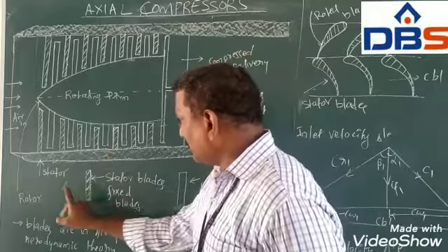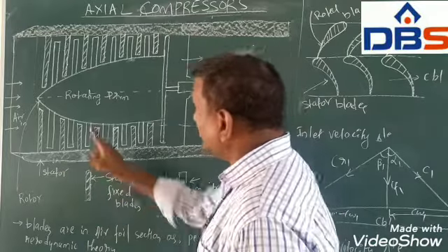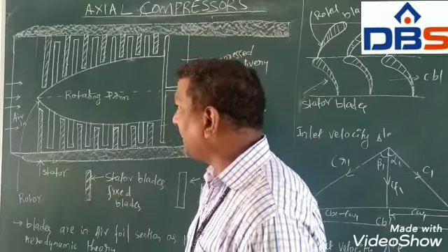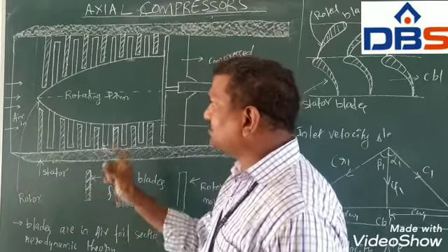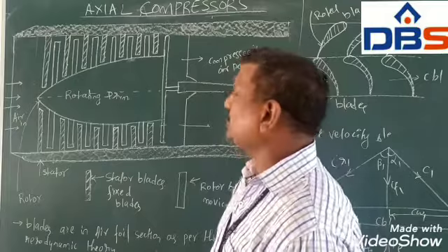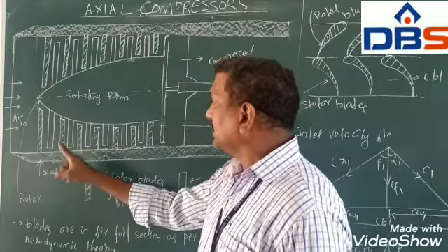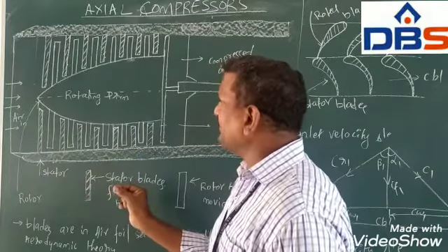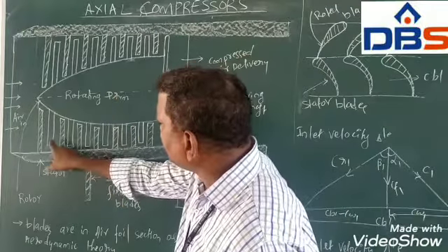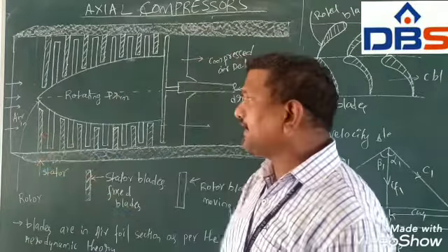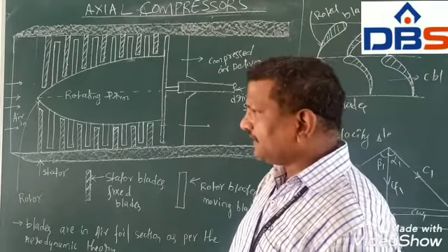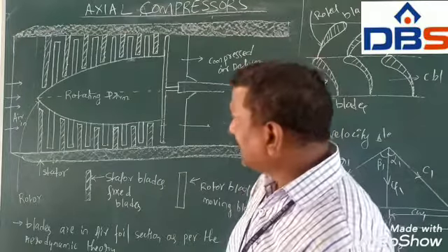What is the function of the stator blades? These stator blades, or fixed blades, convert the kinetic energy of the air into pressure rise, and they also guide the air to flow to the next stage of moving blades at a designed angle. The angle of entry is a very important factor.